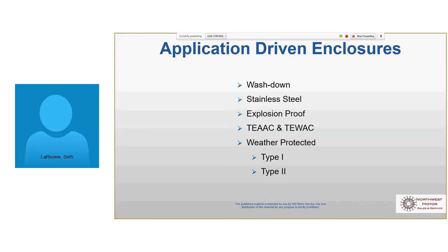And then totally enclosed air to air cooled, totally enclosed water to air cooled. Those are big machines, thousands of horsepower. The reasoning there is when you just put a fan on the opposite drive end of the motor and it's blowing air across, if it's a big motor, maybe 7 or 8 feet long, by the time the air gets over here, it's already warm. It's dissipated heat across the skin of the motor, and it's not cooling this bearing nearly as well as it's cooling this bearing. So a totally enclosed air-to-air heat exchanger is a top-mounted device that sits over the motor that blows air over both bearings and then out through either the sides or the bottom.